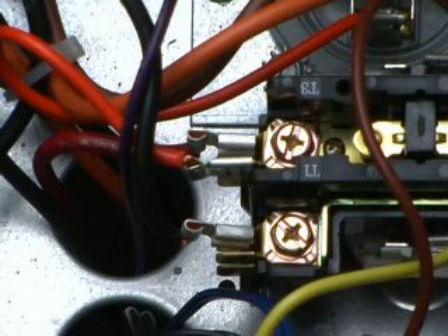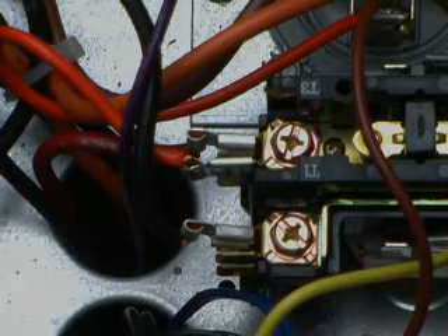So in that situation, like I say, at that point you don't know. The compressor may in fact be locked up. Unfortunately, unlike fan motors, where we can put our hand on the blade or the wheel and spin the motor to see if it's locked up, you can't do that with the compressor. So rather than directly confirming a locked up compressor, you just eliminate the electrical problems that can give it the symptoms of being locked up.